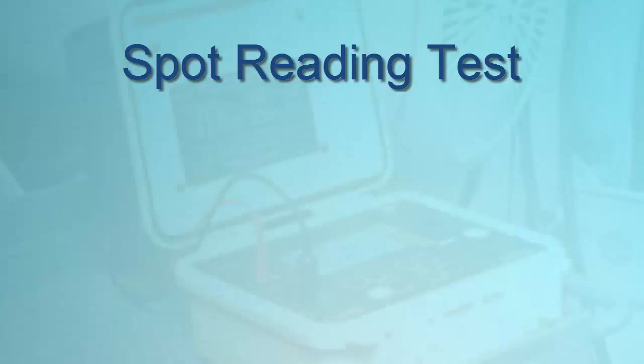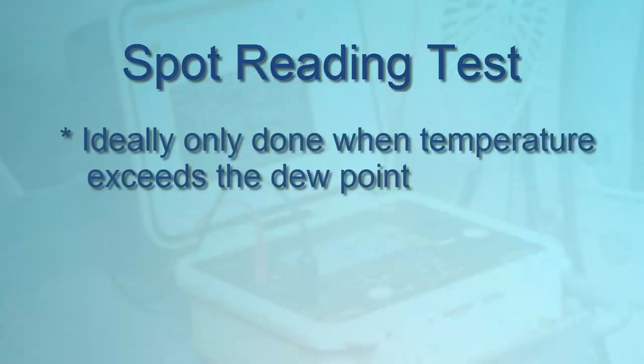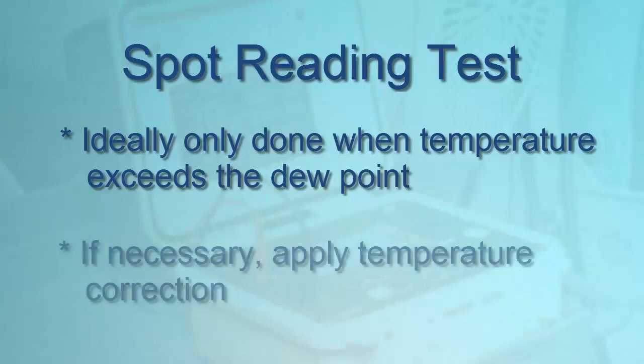To ensure your results are valid, spot testing should ideally only be performed on systems with temperatures exceeding the dew point. If tests are performed at different temperatures, carefully record the temperature of each test and apply the appropriate correction to determine what the resistance would be if the tests were performed at 20 degrees Celsius, or 68 degrees Fahrenheit.